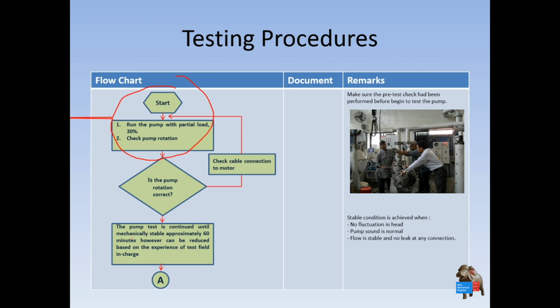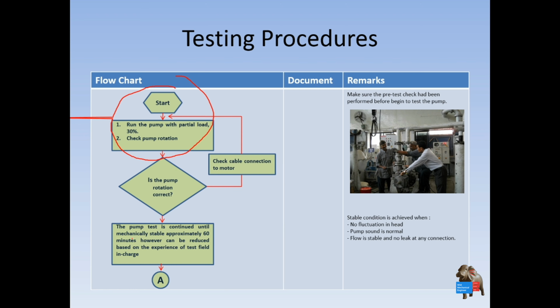Then you need to check whether the pump rotation is correct or not, but you don't actually need to wait 10 minutes to check the pump rotation. You just see how the shaft rotates compared to the correct pump rotation. If it is wrong, you have to modify it. If your pump rotation is already correct, then you continue until it is mechanically stable. Let's say 60 minutes, but I think 60 minutes is too much. Based on my experience, only 15 minutes to wait for everything to be okay, and to check that the pump bearing is not so hot and the vibration is not so high. And then we continue.